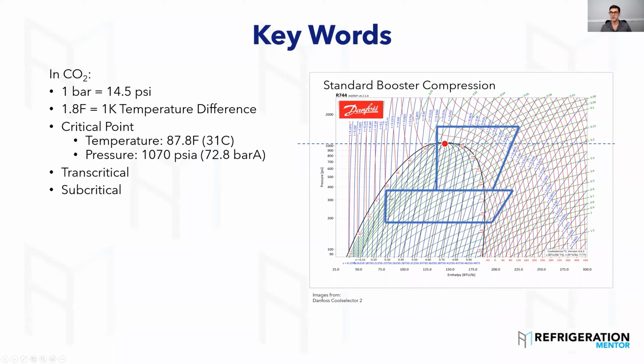Subcritical. That's where all our refrigeration equipment works now. So if you work on 404, 448, 449, 134A, we're always running in the subcritical zone because that critical point's so high. So it's really important when you talk about a booster system, you're going to have the medium temp, which will go into transcritical, and then you have your low temp, which is going to stay in subcritical. So that's your freezers. Any questions so far?